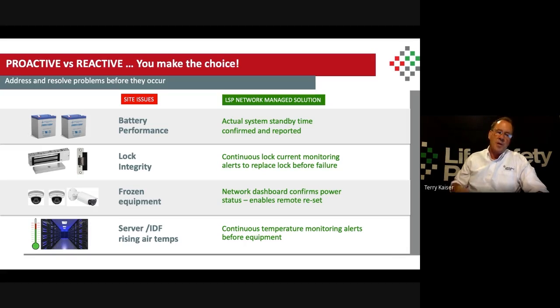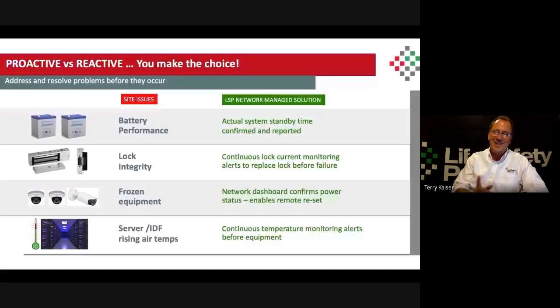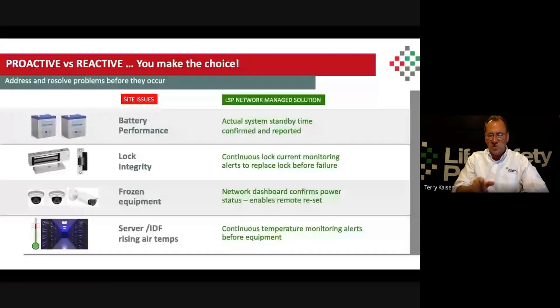The other way is, when you test to see if the batteries are still good two years later, you send a tech over. You guys unplug the terminals, put a meter test on them, test the batteries. That's not under load. The proper way of doing it is to test these batteries under load, what you rated those batteries for, how long to keep those 8 doors up for 4 to 6 hours.